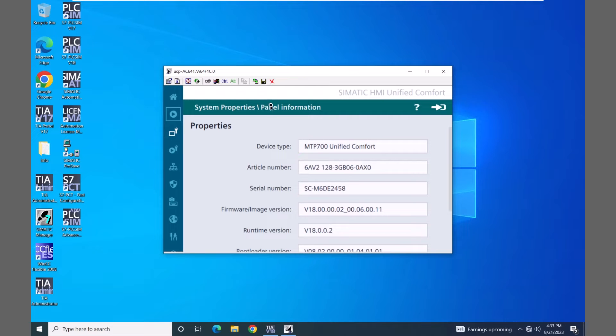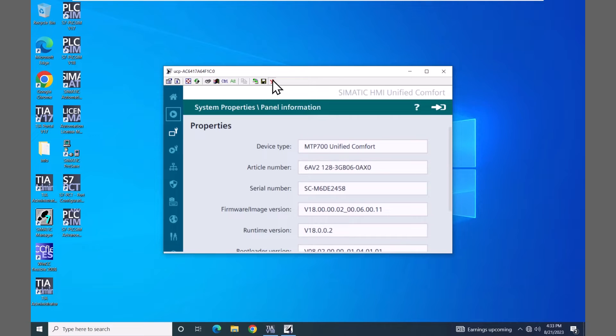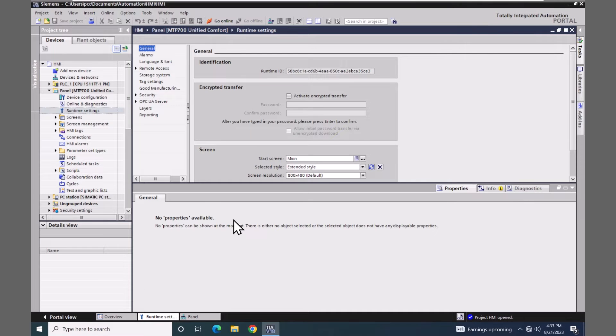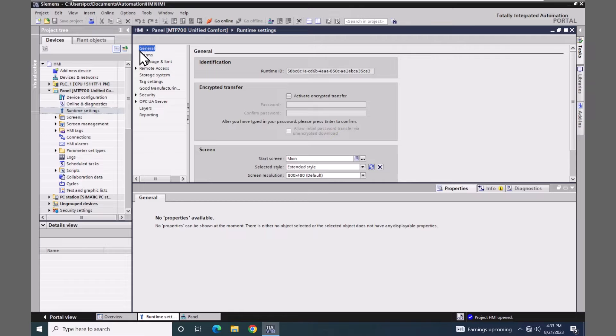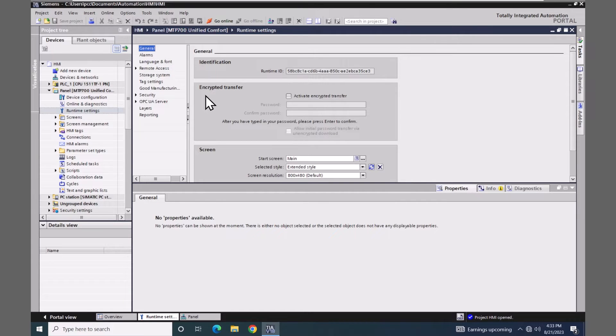I'm going to close the smart client software and open up TIA Portal. Underneath the unified comfort panel, the runtime settings, and then the general area, there's a section for encrypted transfer. This is where you can activate the encrypted transfer and enter in the password. This must match what was entered in on the panel in order for the transfer to take place.